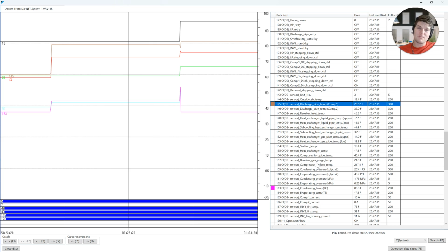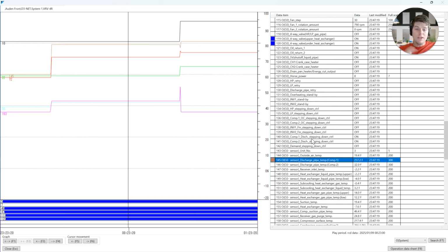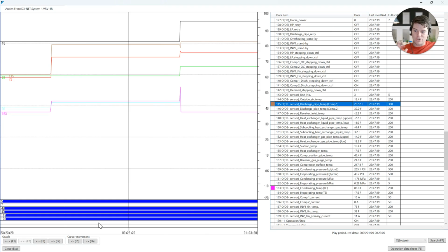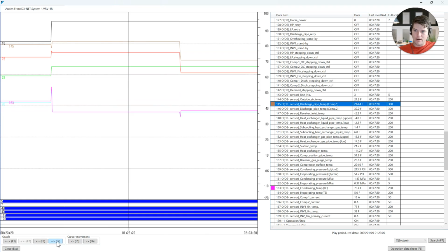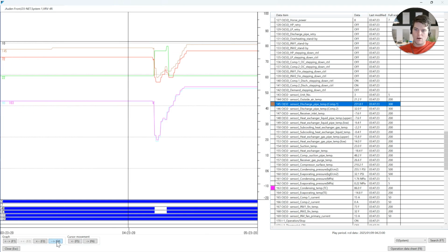Because remember, now your name's tied to this. This is your job. You own it. You own this process. If you see this and you know it because science tells us it's cooked, then it's your job to report it and make a recommendation of changing all 4 compressors in this system. Now, there's only 3, 2 in the master, 1 in the sub. I see that because of discharge temps. But either way, that is the discharge temperature and discharge superheat as a whole, and how we look at that and the way that the oil breaks down and the issues that go along with something like that over time.